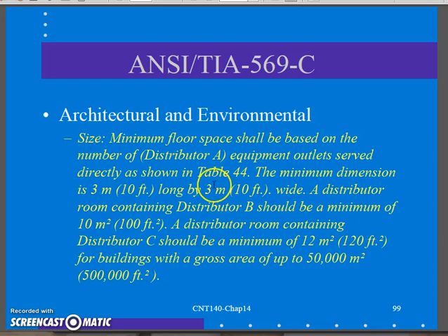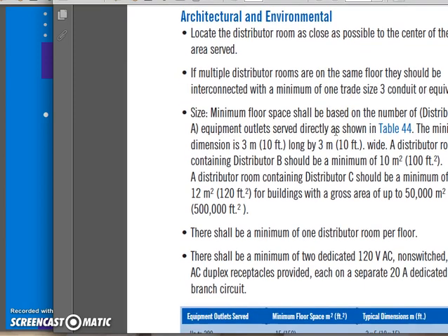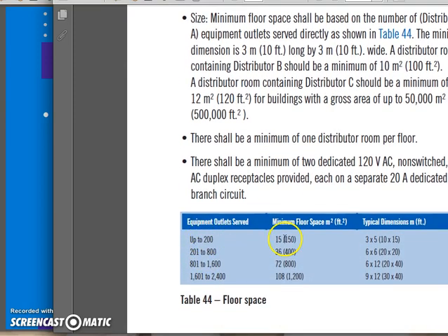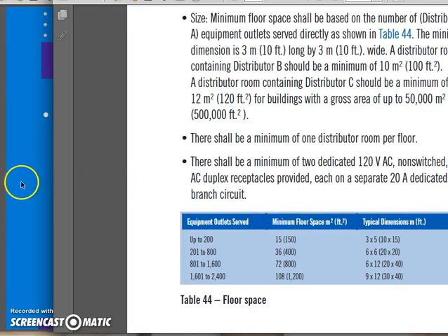They talk about the size of the closet. Your closet should be a minimum of 10 by 10. The more connections and users you're connecting up, the larger the closet needs to be. There's a chart: if you're serving up to 200 outlets you can get by with a 10 by 15 closet; if you're dealing with 200 to 800 outlets, you should have a 20 by 20 closet, and so forth. These guidelines account for the fact that more drops mean more distribution racks, which consumes more room, so your closet needs to accommodate that.